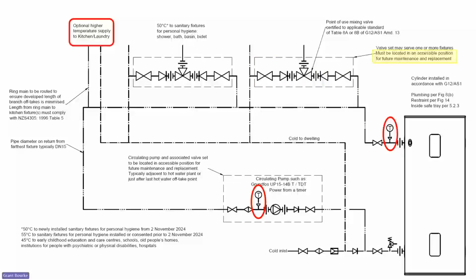If we look down at the other end of the ring main here, and it might be the first, it might be the last, it can be anywhere, the offtake point to the kitchen. Obviously, we can go at higher than sanitary fixture temperature for that. However, what we suggest is having a chat with your client about what temperature they actually want to come from the kitchen sink, and you may want to put another mixing valve on those fixtures because the temperature of the hot water plant may be too high for what they want at the kitchen.